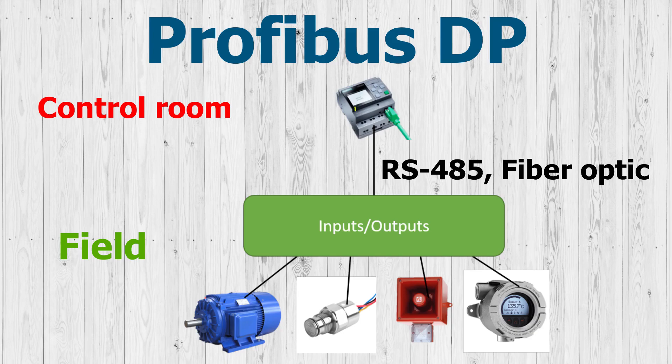Later, Profibus DP, or Decentralized Peripherals, was created to standardize industrial communication through a protocol capable of sending complex communications in a simple way, with a simpler configuration and faster messaging. The difference between Profibus DP and FMS is that with Profibus DP, the inputs and outputs — also called peripherals — of the instruments are not in the control room, but in the field; that is, they are decentralized, which reduces the necessary length of the cables to the instruments.